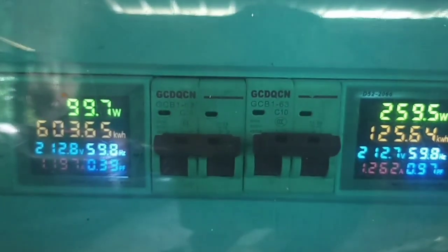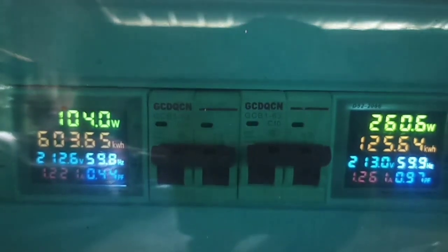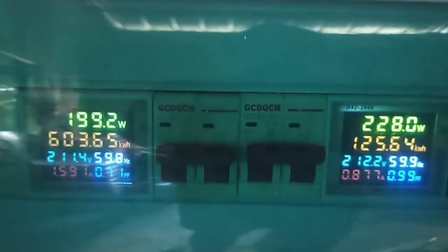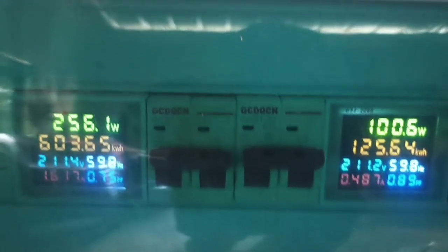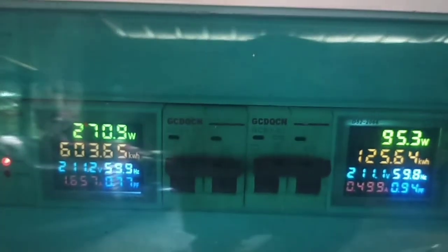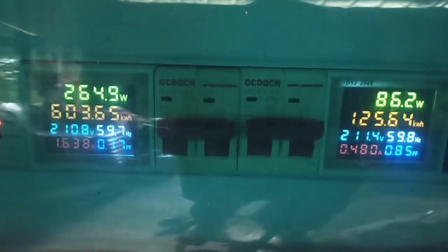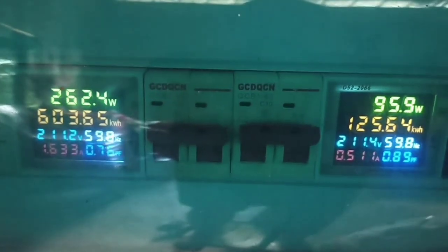This reading from the left is the excess power or the support power from the grid. Excess because I am not limiting the output current from the inverter. So if my max harvest exceeds my total consumption, the rest will go to the grid. This is the result if the current limiter or the CT is disabled.